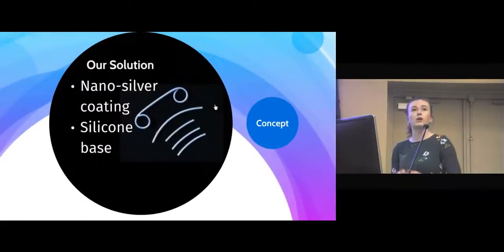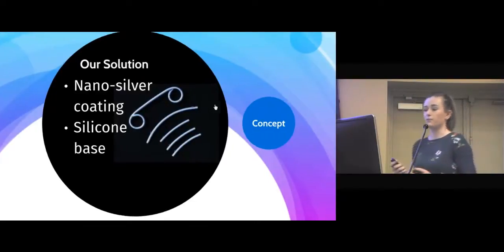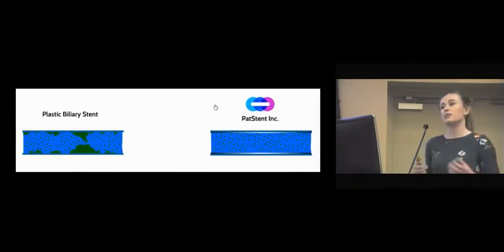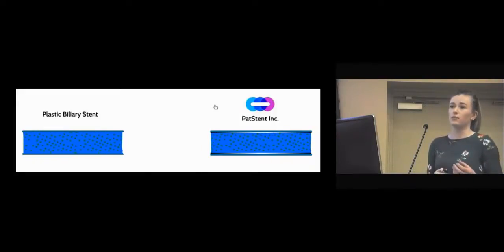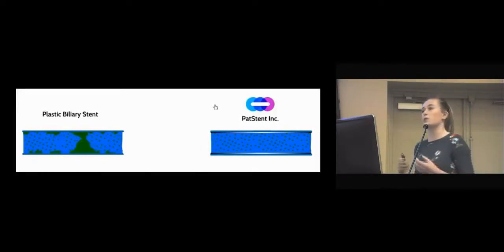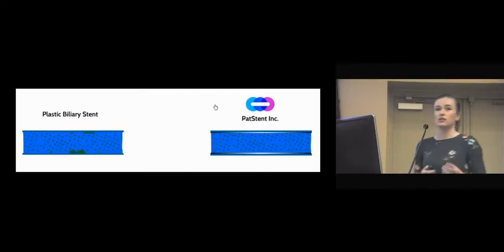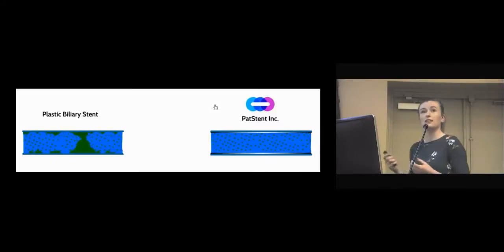Which brings us to why we are here today. At the start of this module, we were tasked with coming up with a cost-effective stent with an increased patency. So we looked at materials that had antimicrobial resistance. We chose silver — it has two and a half times the antimicrobial resistance of any material currently being used in stents. For cost-effectiveness, we used a nano-silver coat with a silicon base. Silicone is highly biocompatible with the body, making it easy to insert. It is also a softer material than current biliary stents, so perforation is a less likely risk.